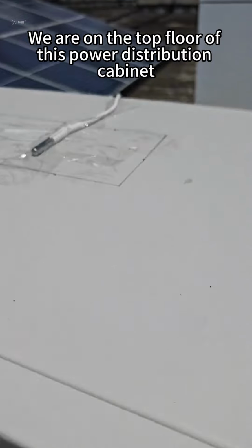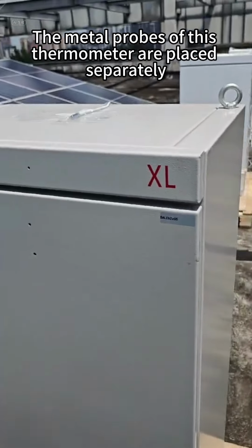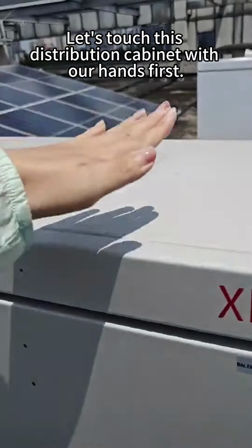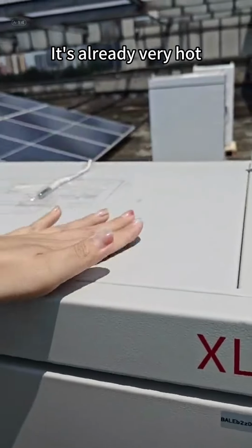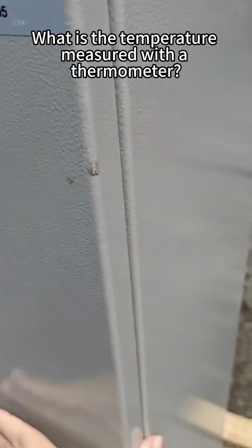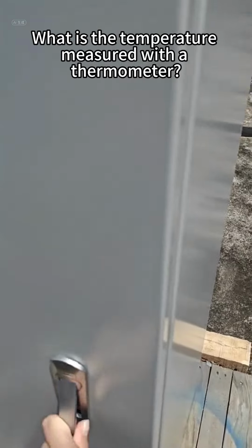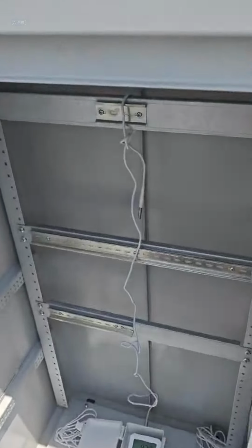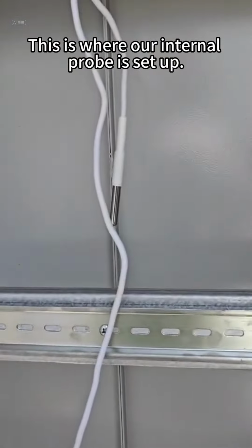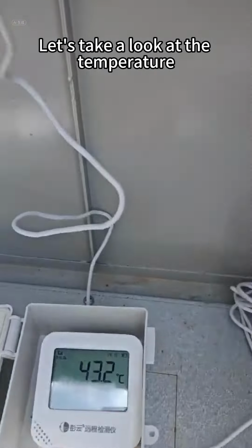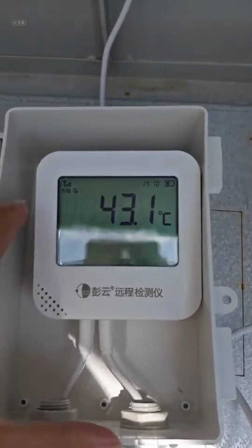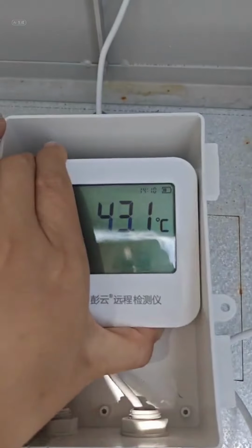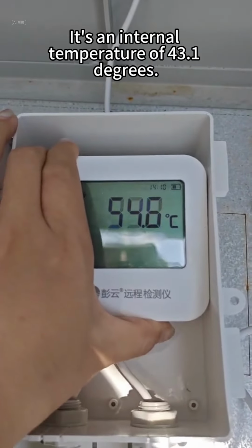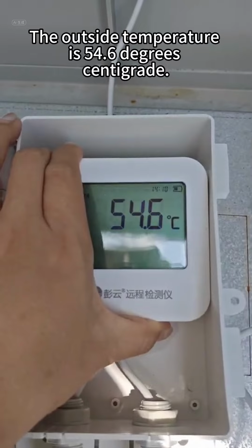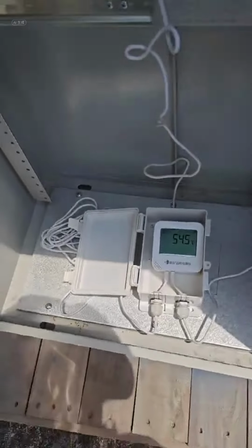We place the metal probe of this thermometer on the top layer of this distribution cabinet, and inside it. Let's touch this distribution cabinet with our hands first. It's already very hot. Let's see what the temperature is measured with a thermometer. This is where our internal probe is set up. Let's take a look at the temperature. It's an internal temperature of 43 degrees centigrade. The outside temperature is 54.6 degrees centigrade.